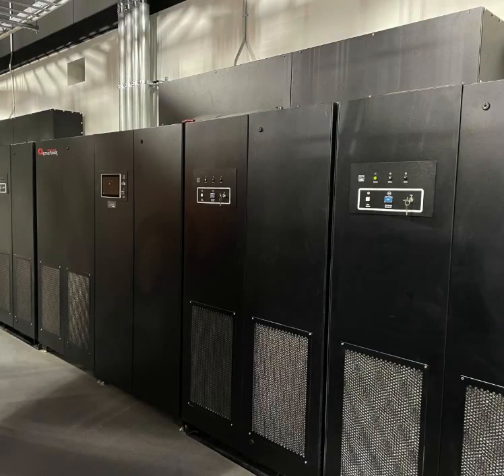We bought flywheels. A flywheel harnesses the power of centrifugal force. Back in the data center there are 4 flywheels operating right now, big heavy drums weighing 4,000 to 5,000 pounds each, spinning so fast. When utility power cuts out, these flywheel drums continue to spin, generating electricity for about 40 to 70 seconds. We only need the first 5 seconds before power cuts over to our generators.